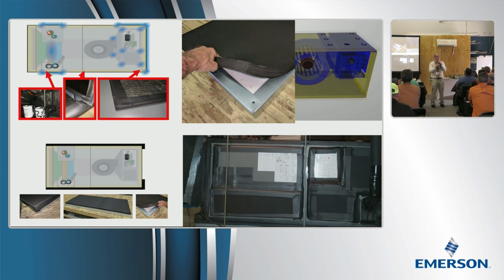This is done for the 65-degree customer whose unit is going to sweat. The factory is going to be no help here. Agreed? If the air handler sweats, how much help is the factory going to be? That's actually how I got into Cold Air is not a Malfunction, because they'd ask, what's your static pressure? It doesn't matter.